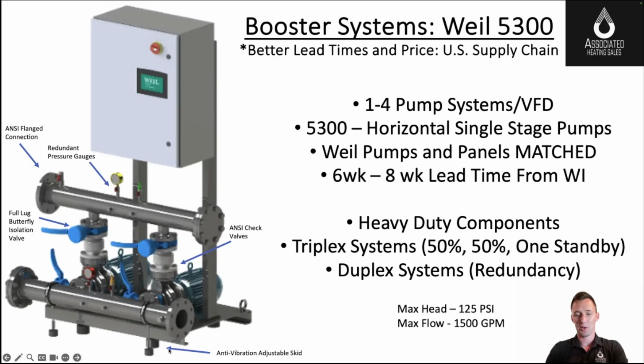On the lower end, which is a nice feature, you have a skid, but you have anti-vibration feet that are fully adjustable. So you'll see some in the market, these booster systems that are just on a metal skid. You worry about noise, vibration, things moving around over time, or putting pressure on your piping. As you move up, the check valve here is a full ANSI connection compared to some threaded or proprietary connection. Really nice to work on in the future, widely available. The full lug butterfly isolation valves here let you work on one side of the system without taking this apart. You'll see some wafer style valves on the market where everything will fall apart when you start to work on it. So these are really nice.